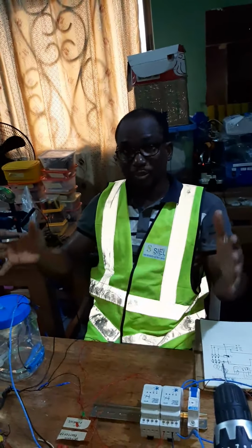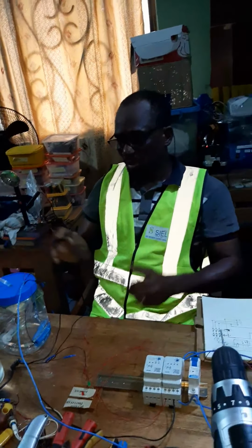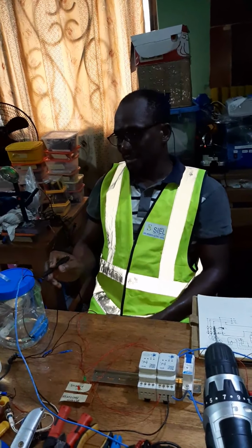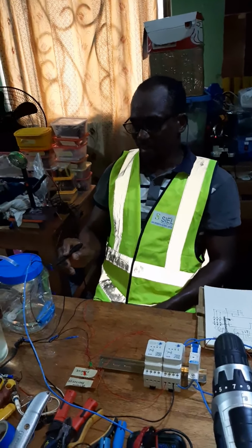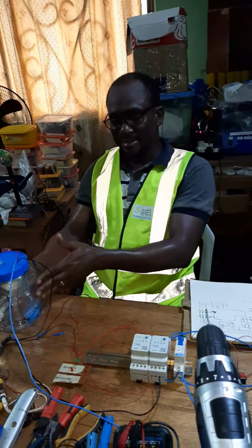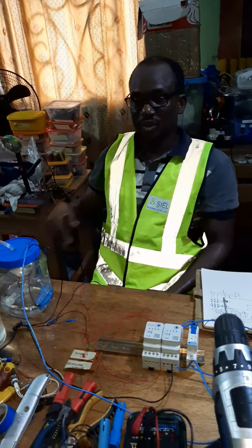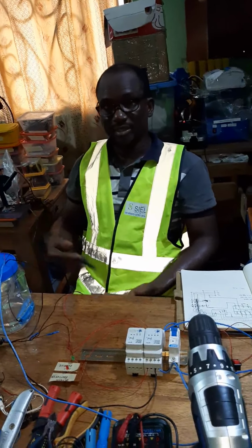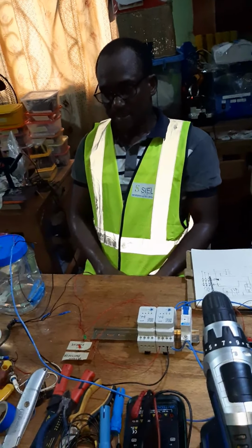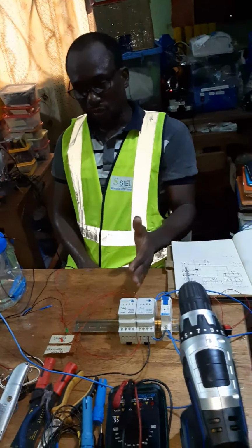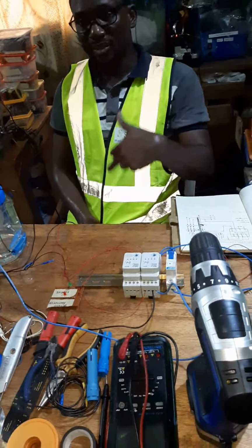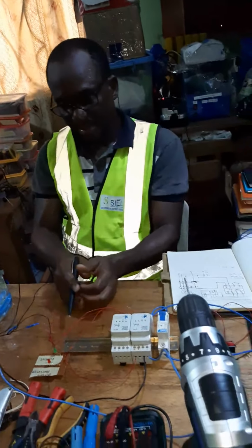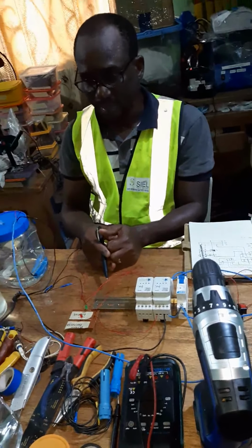Meanwhile, being that it's in automatic mode, the sensor sensed that there was no water in the raw water tank, and it sent a signal to the pump to be running. So the pump ran continuously, ran dry, and eventually it got burnt. Now the problem is under control, but to mitigate against such a situation, we are trying to come up with a dry run protection for the plant.